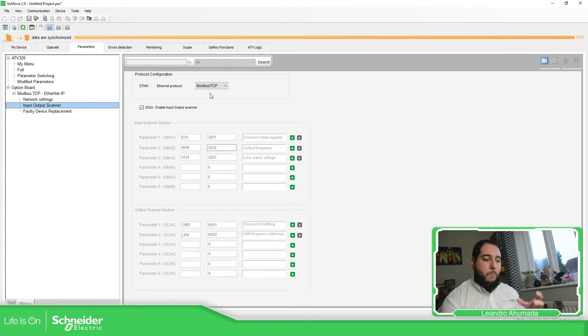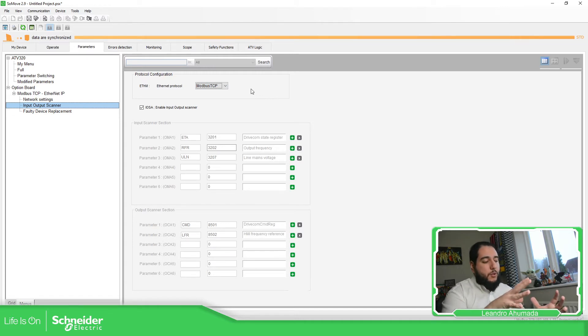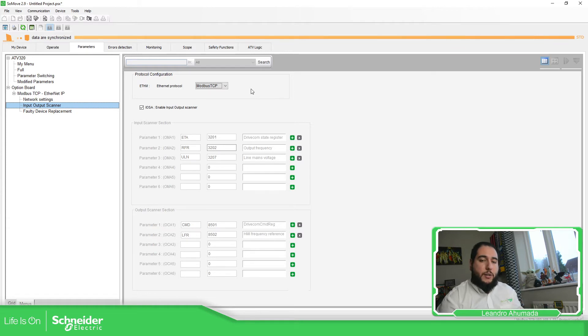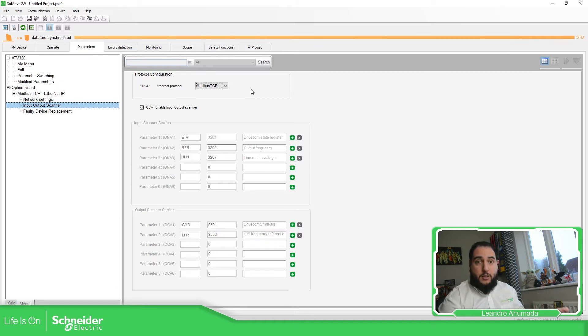If you have this communication module, the only thing we have is the possibility to select EtherNet IP or Modbus TCP. In my case I'm going to use Modbus TCP. This is only related to the configuration for the Ethernet port and how the device can access and exchange data. On the drive, we need to define where the set point and the control come from. By default, you have the frequency coming from the analog input and control by the terminal blocks on the drive.